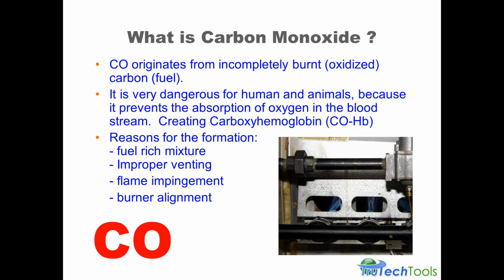CO comes from not having enough oxygen available, and that can be when the fuel is running through too quickly to completely combust, or a fuel-rich mixture. It can come from improper venting, when there's not enough draft being provided to pull the right amount of combustion air through the system. It can be caused by flame impingement. We talked about having to have three things: the right amount of oxygen, fuel, and a source of ignition or heat present to make that oxidation happen. If flame is impinging, it's taking away some of that heat energy, and that will cause a cooled flame, which can cause carbon monoxide formation. Burner alignment also, as you can see illustrated in this picture here, can cause some flame impingement. It can also cause the combustion airflow to be incorrect and cause some carbon monoxide production.